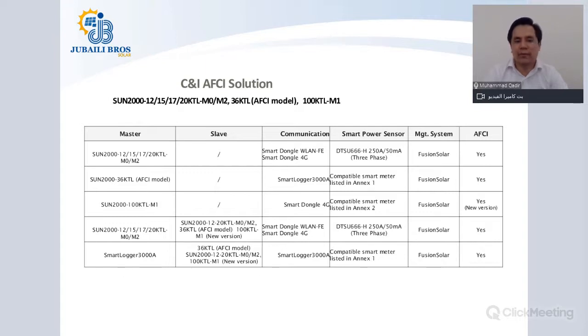Smart Logger 3000A: when you have it as a master device, then you can have all the inverter models that support the AFCI feature, which is from 12 to 20 kilowatt, the 36 kilowatt with AFCI model, and the new version of the 100 kilowatt size, which also supports the AFCI. So the smart logger itself will act as a remote monitoring device as well. It will log the data and send it to the FusionSolar cloud. The smart power sensor and management system are common to the previous case.